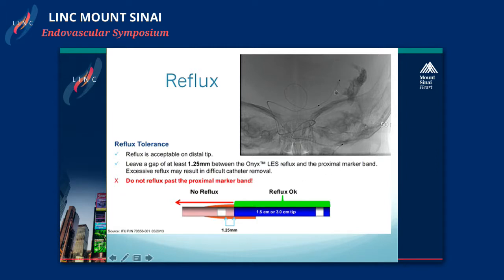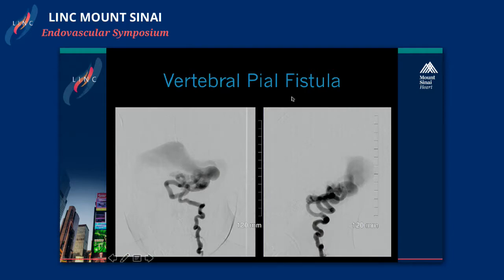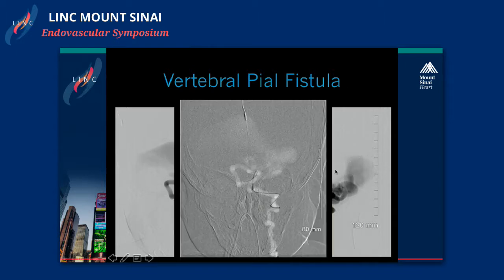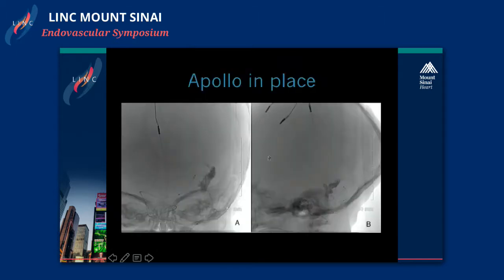This catheter comes with two tips. The proximal marker is where the detachment zone is, so if you reflux all the way to that point during injection, you have to stop or you'll glue that detachment zone in place. This is an example of a vertebral pial fistula — an AP and lateral view of the vertebral artery in the neck and its fistulous connection to a posterior fossa vein. The Apollo catheter is navigated to the fistula, and NBCA is injected. This catheter can be used with both NBCA and Onyx.